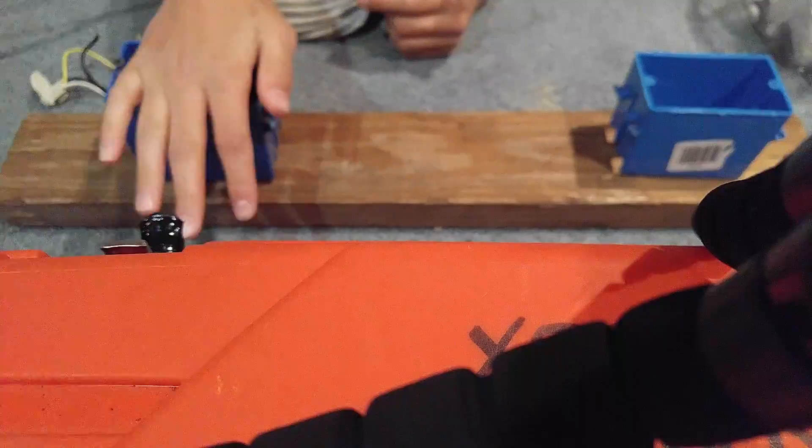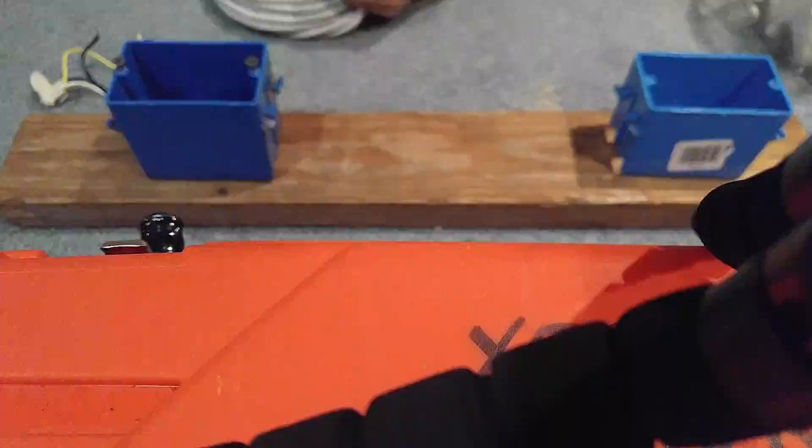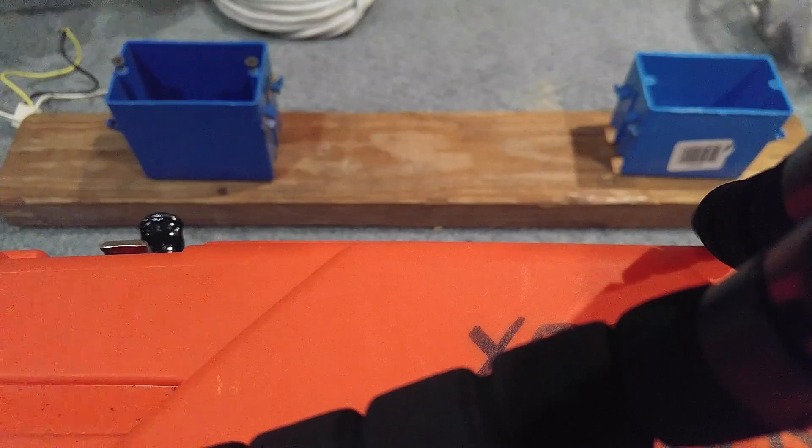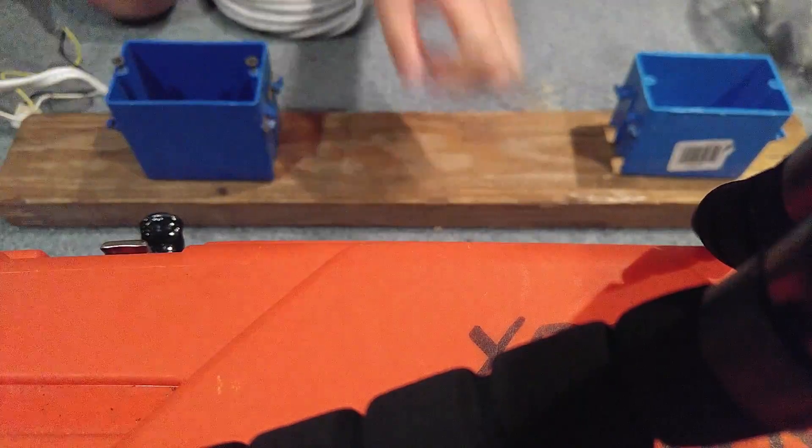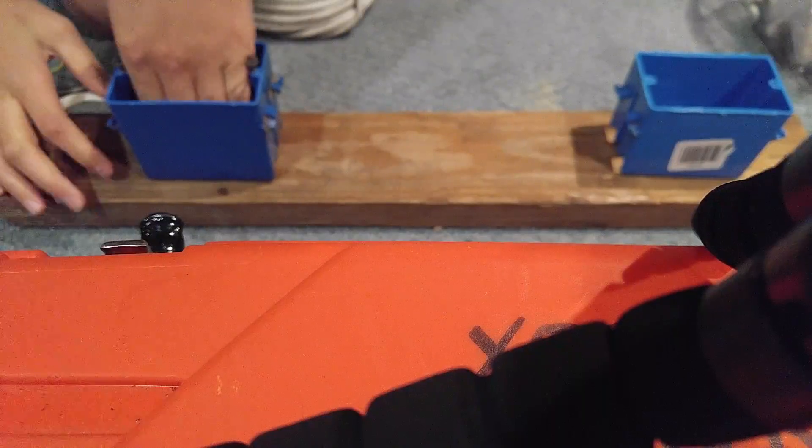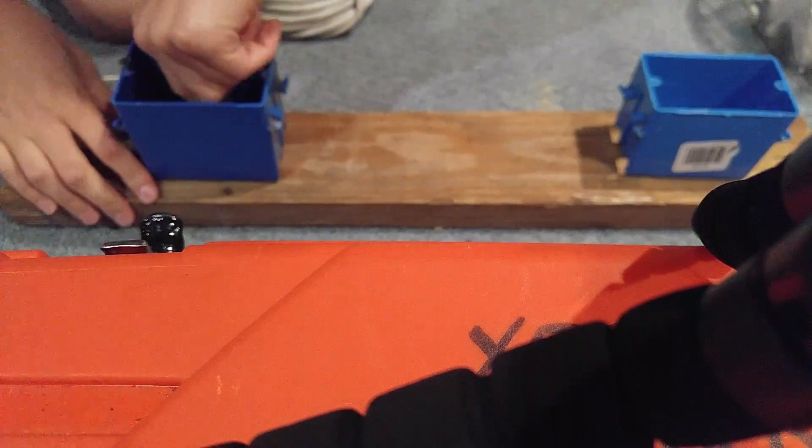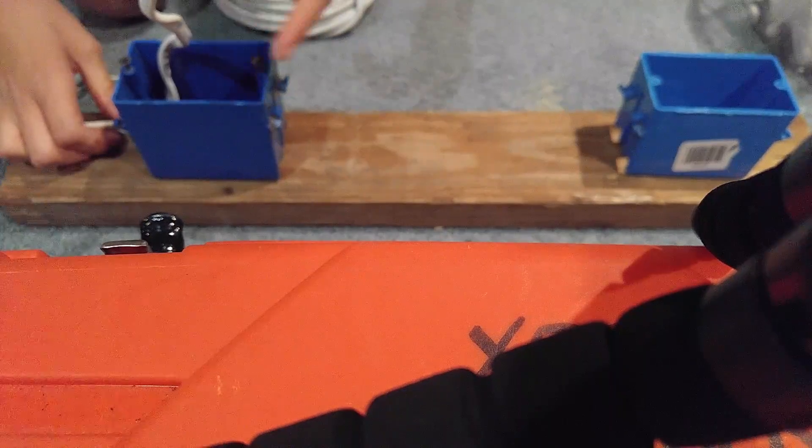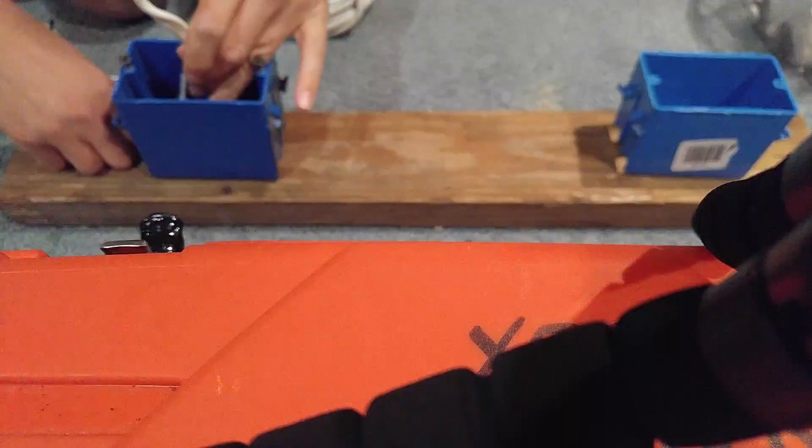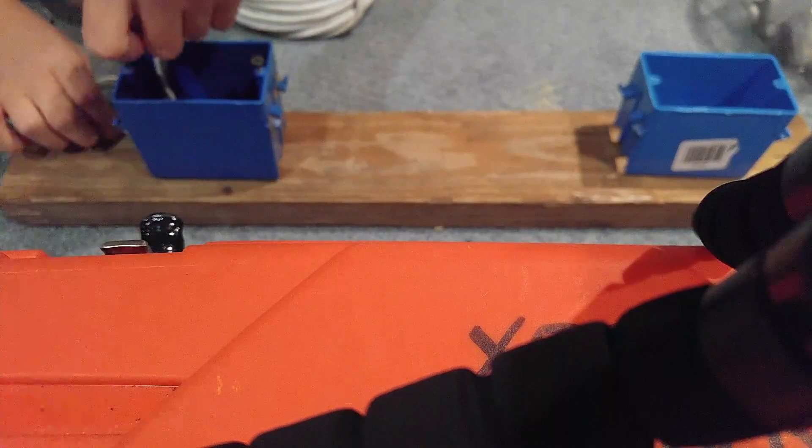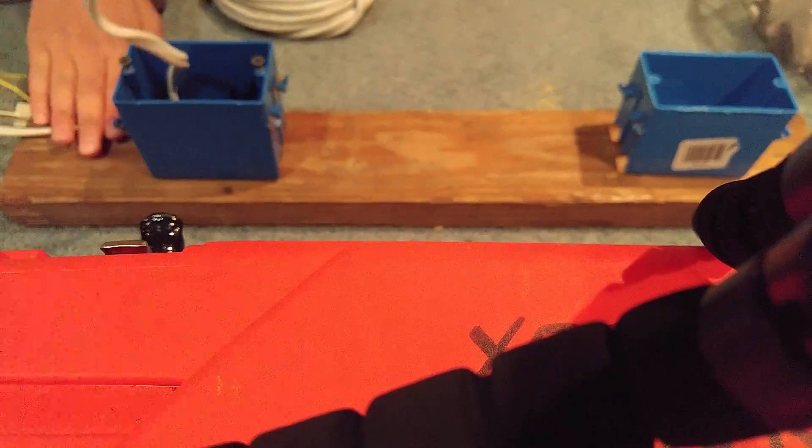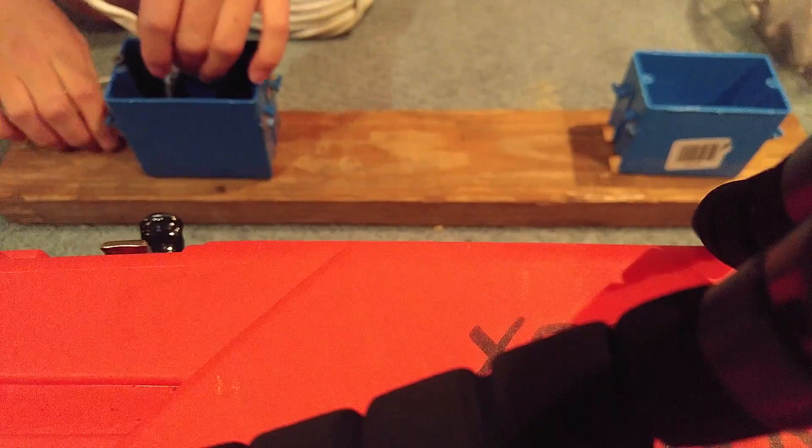I'm going to show you how to get this wired up. To your first box, to your first smoke alarm, you're going to need a 14-2 wire. Bring a 14-2 wire into the box, knock out one of the knockouts. Make sure you lay out your boxes folks. Pull some wire through. You need roughly six to eight inches out of your box. You can always trim it if you don't need too much. You can pull some through.